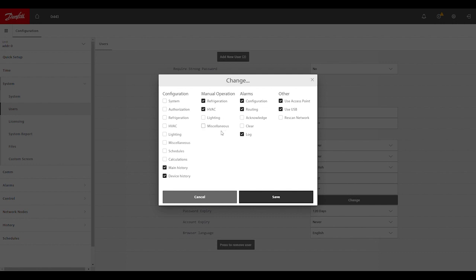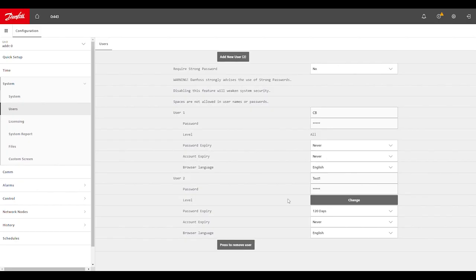or put a case in defrost. For some of the secondary fields that we have in the program - things like alarm routing, acknowledging alarms, re-scanning the system, or even using USB - we can enable and disable what functions are tied to this account by enabling or deselecting these checkboxes and then clicking save.